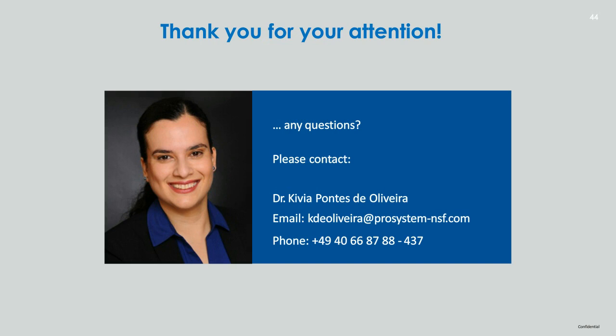Okay, very good. Someone here has asked, what are medical alternatives and are similar devices from competitors also medical alternatives? Medical alternative is also a term from the MEDDEV 2.7/1 Revision 4, which is mentioned in the regulation as available alternative treatment option. So it does not mean the direct competitors, which use the same technology, but other technologies available in the market which are used for the same intended purpose.